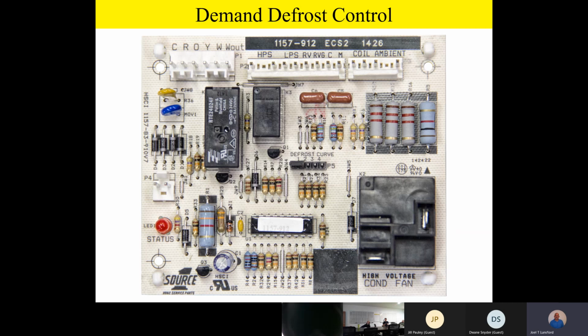We're going to output 24 volts from the board to bring the heat strip on inside, or bring the auxiliary heat on if it happens to be a dual fuel system with a furnace. It'll output W from the board, or W out from the board, to bring on the auxiliary heat during defrost, so you don't freeze the homeowner out during defrost. Because remember, when you go to defrost, you're actually going into the air conditioning mode to defrost that outdoor coil.